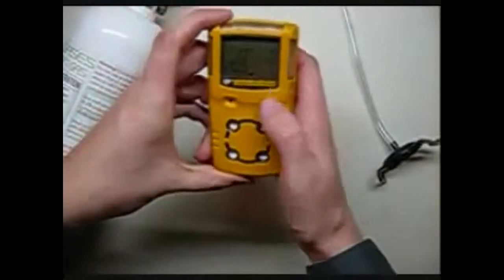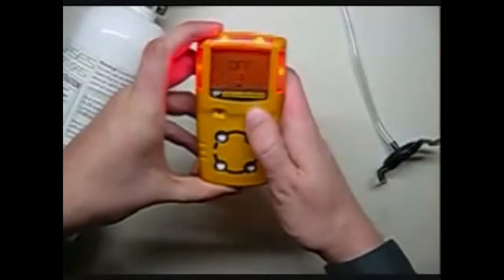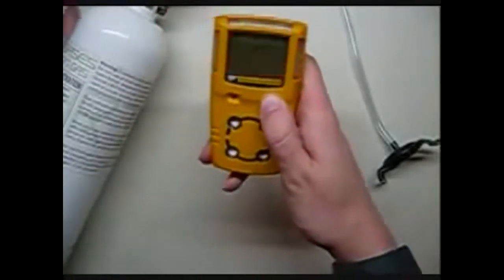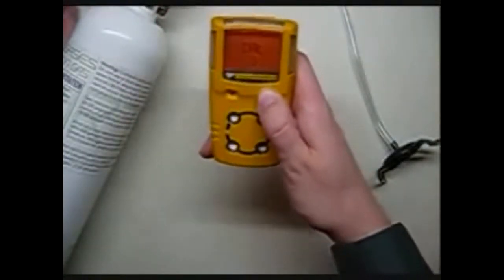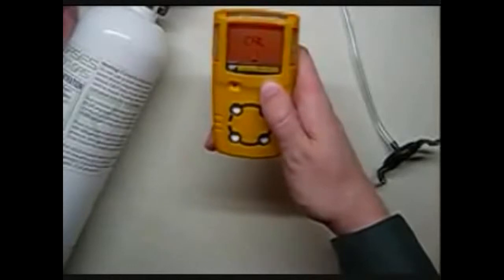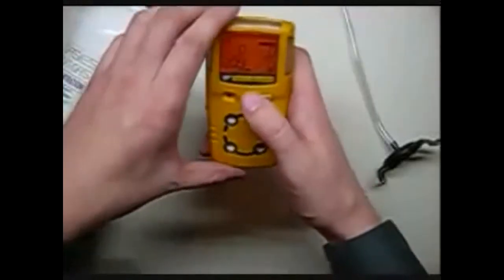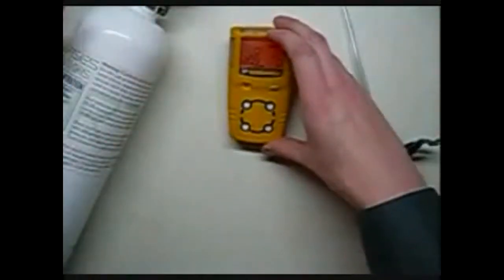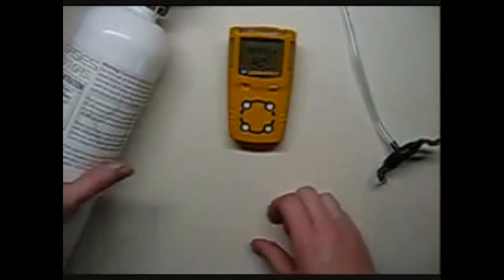Now to calibrate the unit, hold the button down for 3 seconds until it turns off, and continue holding the button. So go into cal mode. Okay, now release once it begins to auto zero. You always want to be in clean air when you do this. Now it says apply the gas.